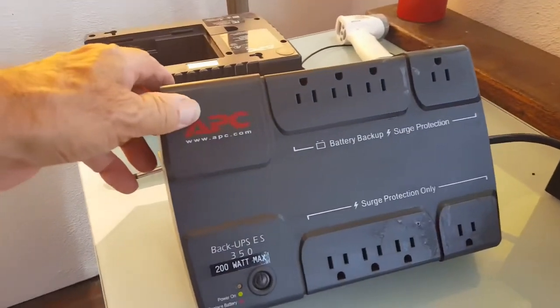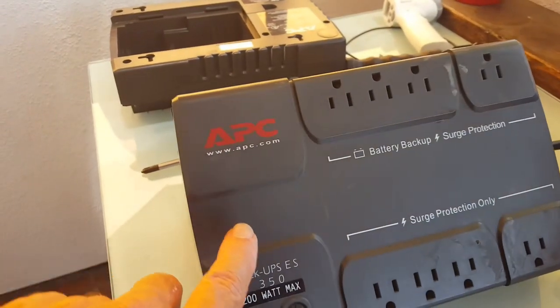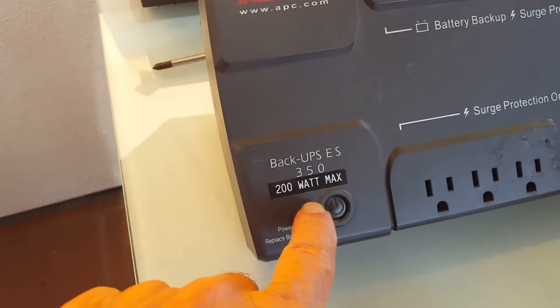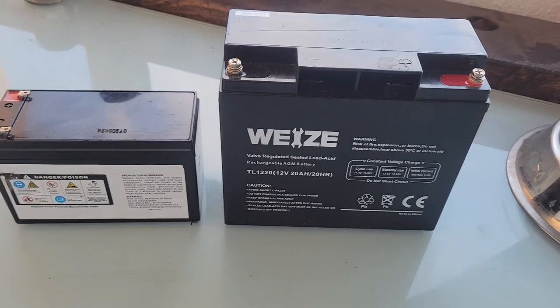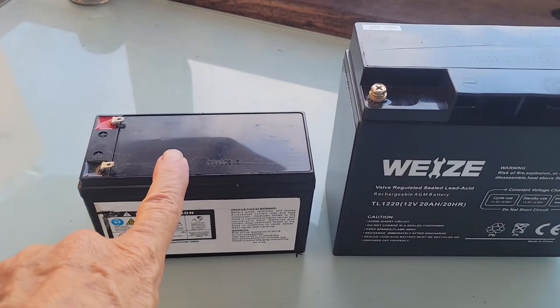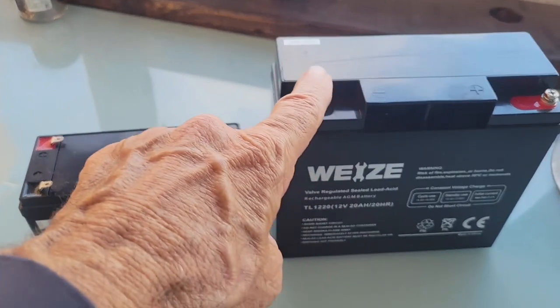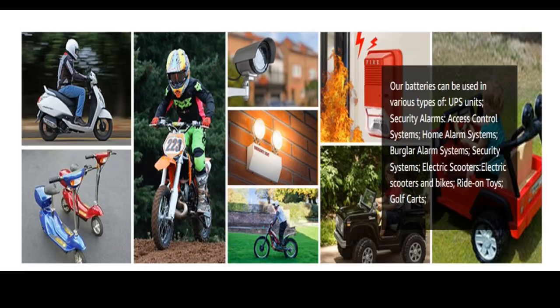We have a UPS, an APC ES350, which is a 200 watt UPS. We are replacing their 7 amp hour battery with a 20 amp hour battery. I chose this battery based on the manufacturer's ad. It's an AGM battery. Although technically it's not a deep cycle battery, depth of discharge on an AGM gel is about 80%, so you wouldn't want to drain it all the way down to zero like leaving your headlights on. But the UPS, I would expect, is going to shut off somewhere around that range.